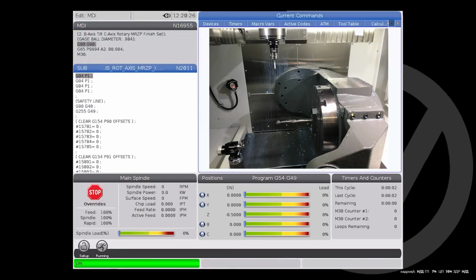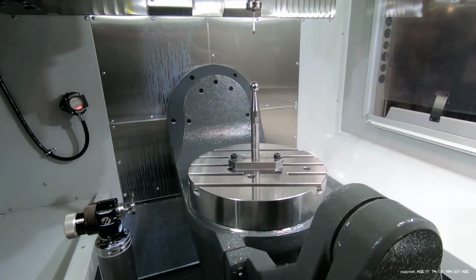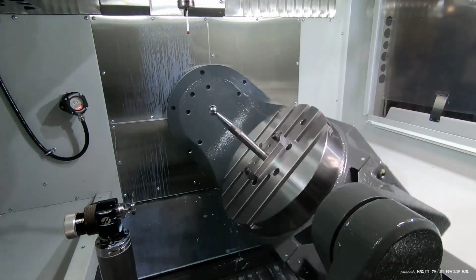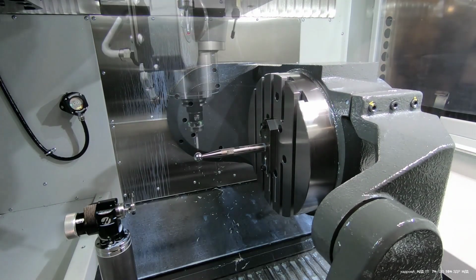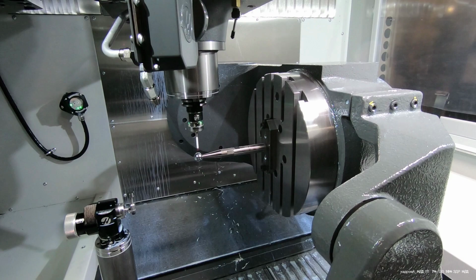The program will ask if you would like to run the UMC B90 MRZP program. Press Y for yes. Press Cycle Start to continue the program. The program will pause after taking all the data points at B 0 degrees and rotating to B 90 degrees. Check to make sure that the spindle will not crash into the platter when it probes the calibration sphere. If the machine will not crash, press Cycle Start.